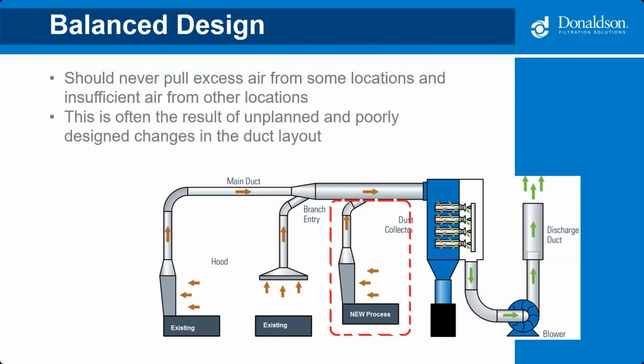Having a balanced system is one of the most important aspects to an effective dust collection system. It ensures you're pulling the required amount of air from each hood. A lot of issues have been created in existing systems when the process owner goes to add an additional leg and doesn't account for the ramifications downstream.